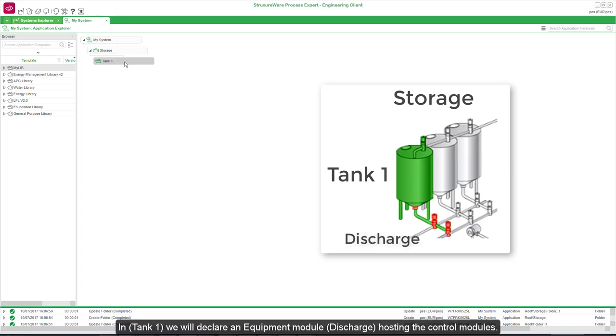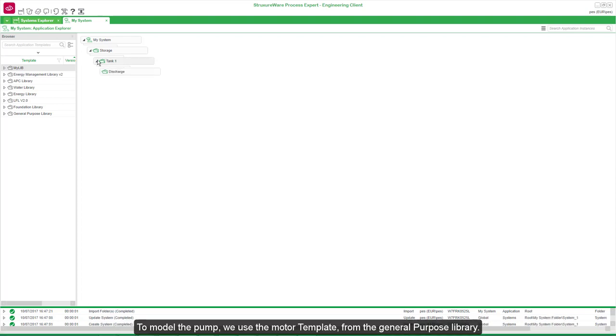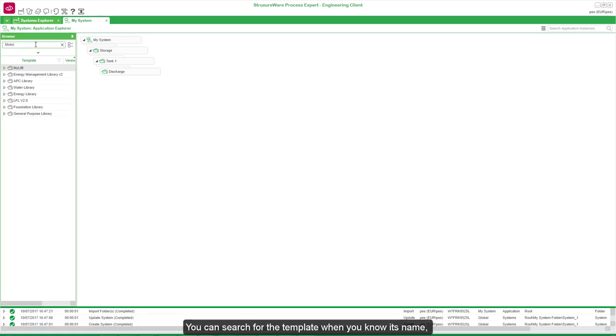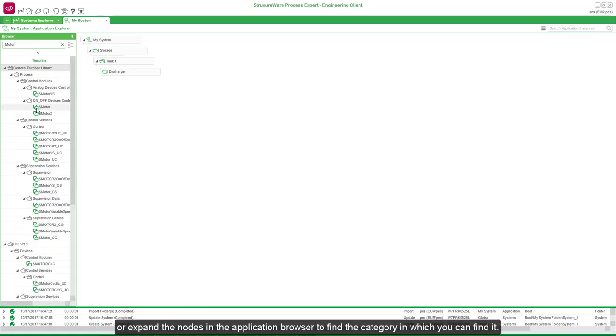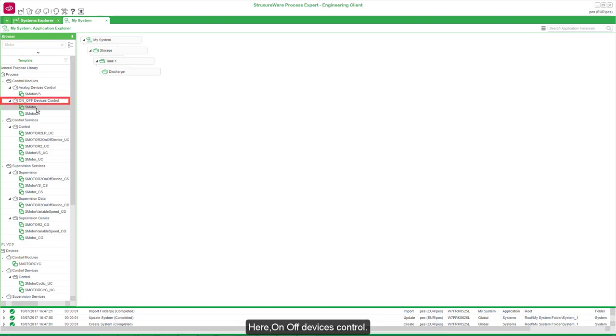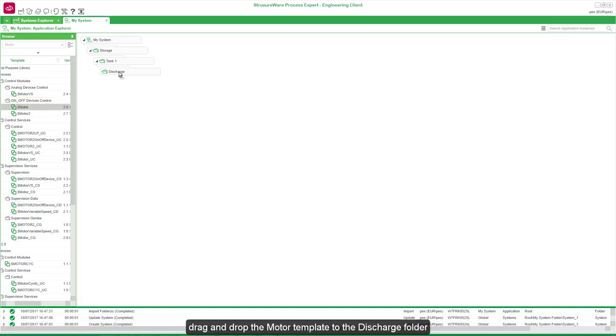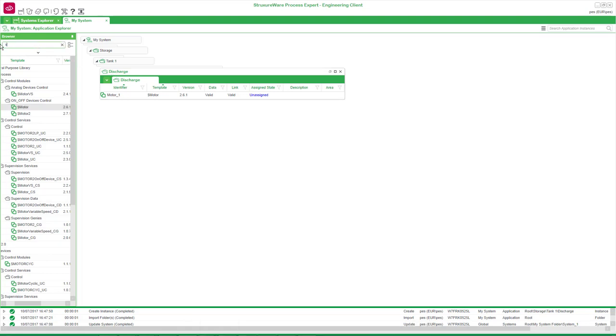In Tank1 we will declare an equipment module, Discharge, hosting the control modules. To model the pump, we use the motor template from the General Purpose Library. You can search for the template when you know its name, or expand the nodes in the application browser to find the category. Here, under On/Off Devices Control, drag and drop the motor template to the Discharge folder. Then repeat the operation for the discharge valve.